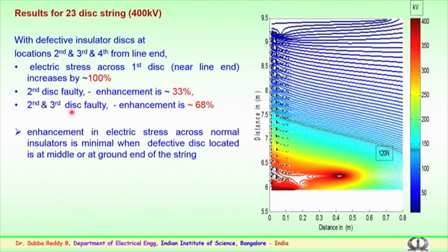So, as the number of faulty discs from the line end increases, leaving the first insulator, if the second, third, fourth are faulty, the stress across the first disc will rise to a very high value. This could lead to early scintillations, early flashover across the first disc. The cascading effect could cause the entire string to flash over.